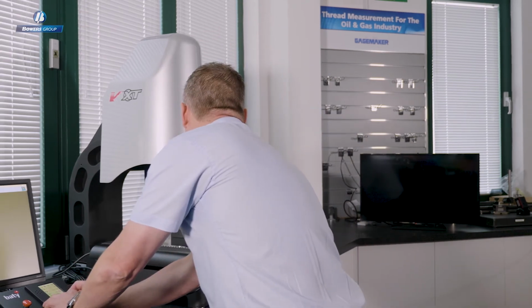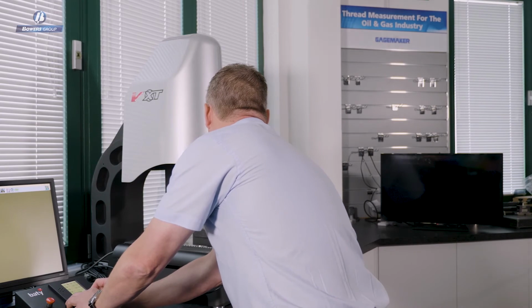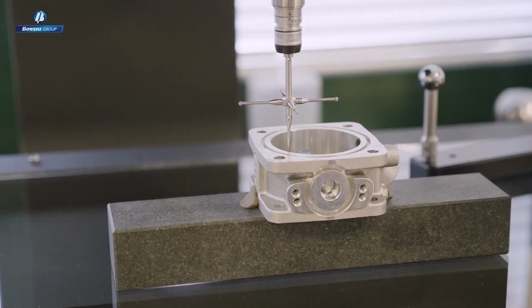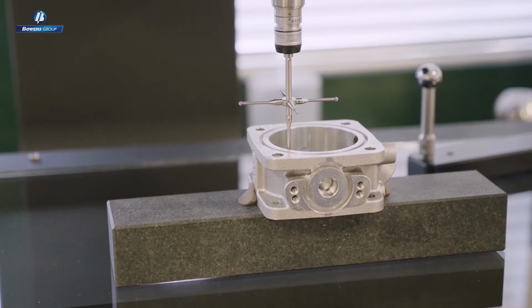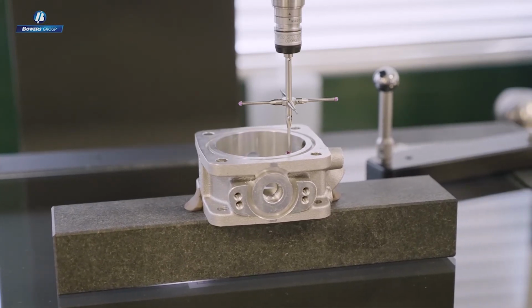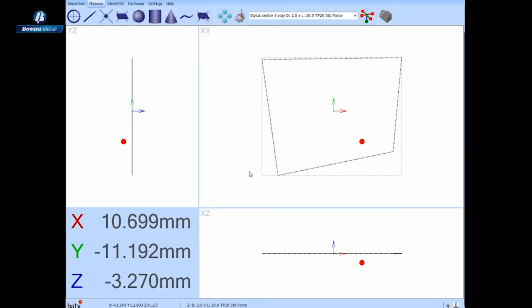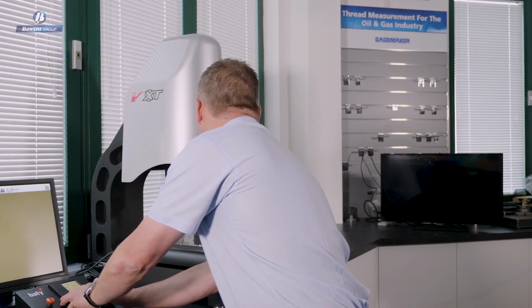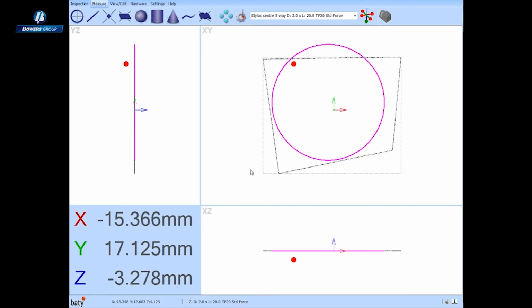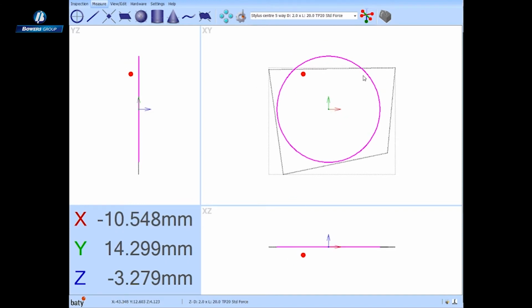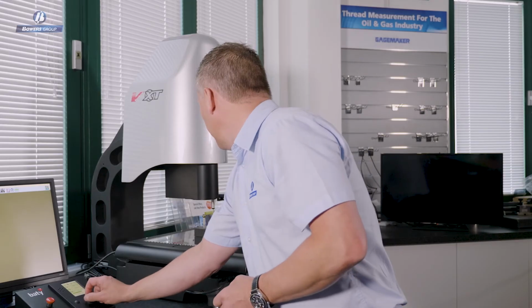So now let's measure a circle. I'm going to call for a circle measurement form, drive the touch probe into the bore, and using the joystick control, I can ensure that probe points are taken at a controlled speed, so I'm not influencing the probing speed of these measurements. I'm just driving somewhere close and asking the machine to finish the job for me. So there's my diameter. We'll call that a reference feature for this template, and let's come out of there.